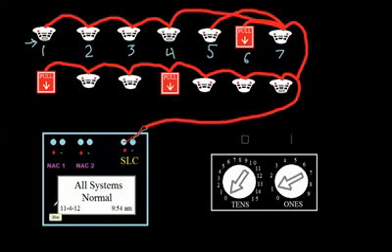But there's a date and a time, which is useful for when you're looking into history. It'll keep a history of all the events. You can go back through and look up, well, what happened? Maybe you're going on a service call and the panel's going into trouble intermittently. In the old days, you wouldn't be able to really tell what was going into trouble, whereas now these panels will keep a history, and you could say, okay, well, device 3 was intermittently going into trouble.